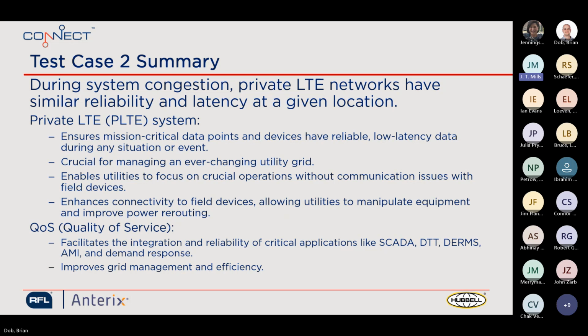And the piece that enables that is quality of service, allowing you to shape the funnel to every device as you deem fit, automatically, as you set up your system. This is all an automatic system that you prioritize when you set up and build your system. And therefore your reclosers and all this data transfer occurs automatically. So your operators don't have to do any of this configuration, right? This is all built into your communications network, further enabling your ability to make timely decisions in real time. Next slide, Brian.